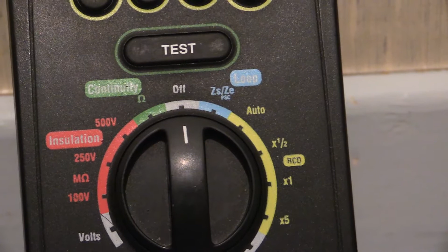And then down the bottom there's another test. There you go, it says ramp. When you choose the ramp function and push the test button, this unit will slowly increase the amount of trip current until it switches off. And when it does switch off, the display up the top will tell you what the trip current was of that RCD. With all these other tests, all they do is tell you how long it takes for it to switch off.